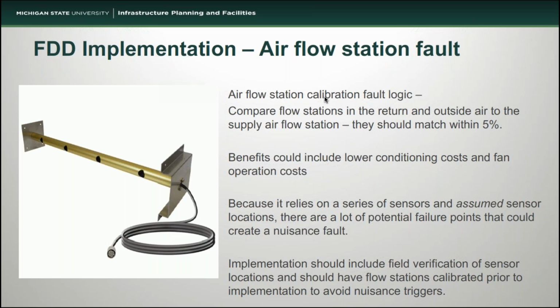I felt like this has a lot of benefits. They include lower conditioning costs and fan operation costs. You can save conditioning energy if you are much warmer or much cooler outside than the temperature that you want in the space, because as you bring that air in, you'll be having to heat it or cool it further than you would if you were mixing the air better. And then fan operation costs can be saved because most systems will have a supply air set point and an outside air set point that they need to meet as a minimum. And if they're bringing in a lot more air than they think they are because the sensor's out of calibration, then we may be moving a lot more air. It uses a lot more fan energy to move that air, whereas if it was in calibration, we would not need nearly as much fan energy.